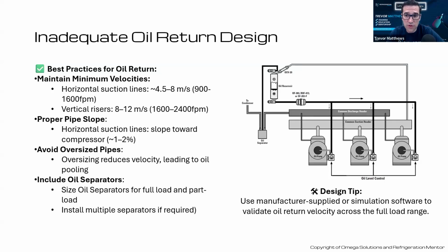So we're talking more on the refrigerant side at this time, but on those oil lines, if you undersize those, you're going to run into a world of issues. And I've seen it multiple times in conversation in courses where they're like, we're just not getting oil on the oil transfer solenoid, the way it opens up.